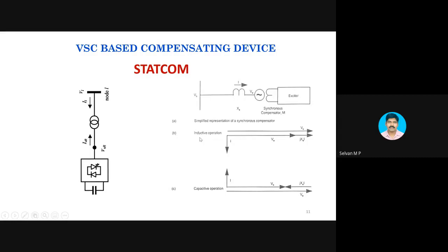So see here, inductive operation. If the STATCOM voltage is less than the bus voltage, then it will act as an inductor. It absorbs reactive power. If the STATCOM voltage is more than the bus voltage, then it acts as a capacitor. It gives you reactive power. Okay, so this operation will happen only if there is a presence of this reactance. Otherwise, it will not happen.